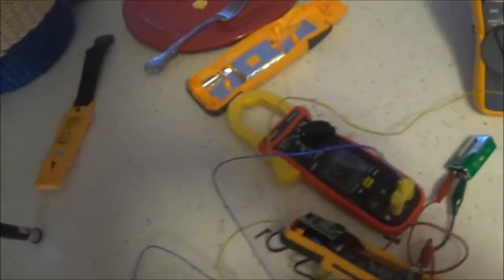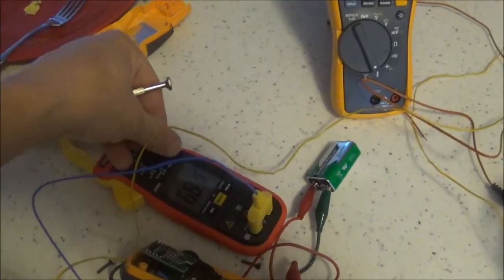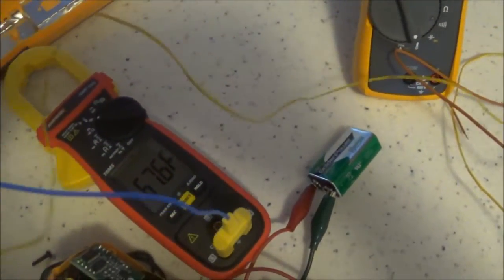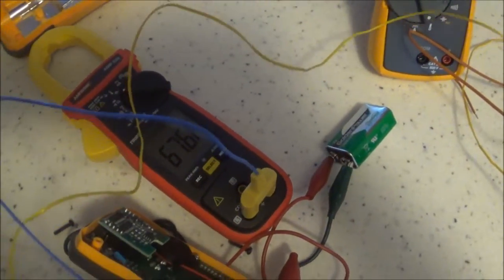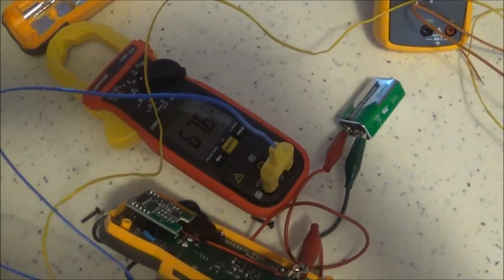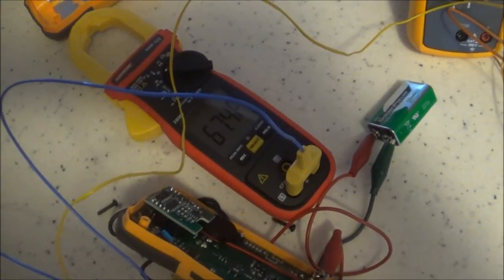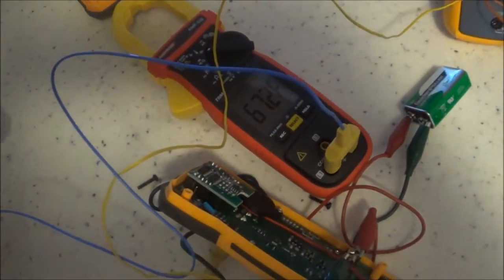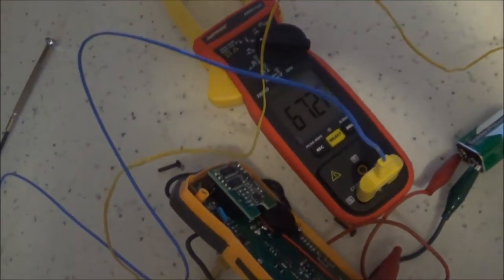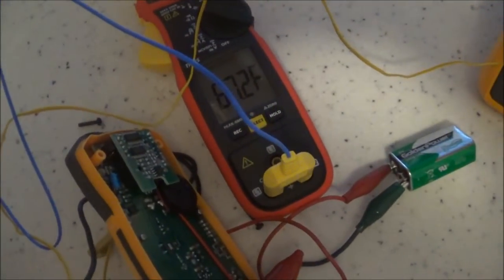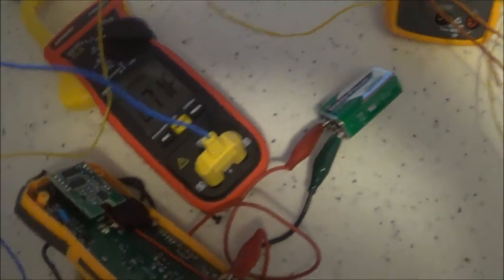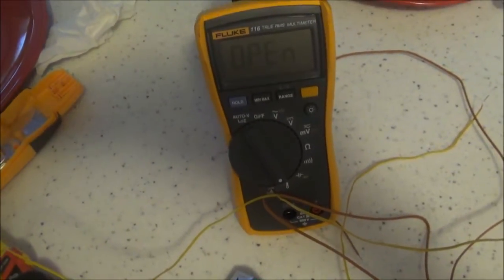So something to note when you are calibrating, you can't really calibrate the Amp320, it's factory calibrated, so you really need to use the one that came with it. I mean if you lose it, just realize if you're using the Fluke product, it may increase the temperature. If it's a degree off at 32, we don't know how much it will be off at a higher temperature. Maybe not so much, but it's going to be off a little bit. Using the factory applied leads, you can see it does make a difference trying to calibrate it at 32 degrees.